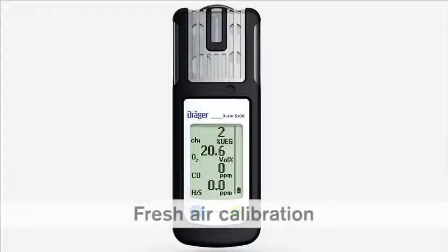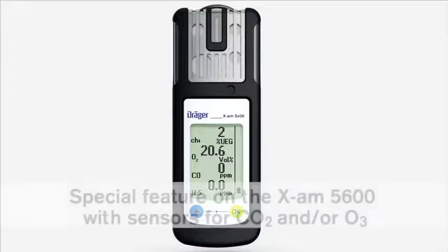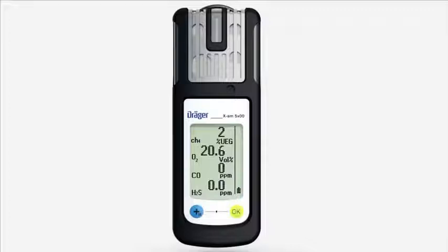You can use the fresh air calibration function to set the oxygen channel to 20.9% by volume and the other sensors to zero. Make sure that you are in an area with clean air when you perform the fresh air calibration. The following additionally applies for the Dräger X-am 5600: the fresh air calibration and zero adjustment are not supported by the Dräger Sensor Dual IRCO2, Dräger Sensor IRCO2, or Dräger Sensor XXS O3.